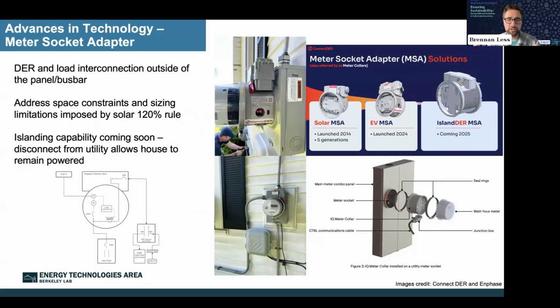So one tool that's emerging, and has been on the market for a little while already, is the meter socket adapter. Initially I think these were out there for solar PV interconnection in cases where we didn't have room to connect through the bus bar in an electrical panel. In some jurisdictions in California it's called a green meter adapter, and every utility has its own regulations around when they permit you to use this approach and where.